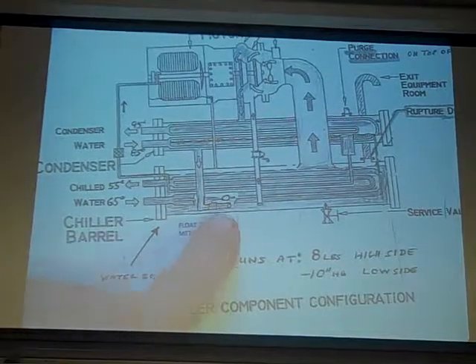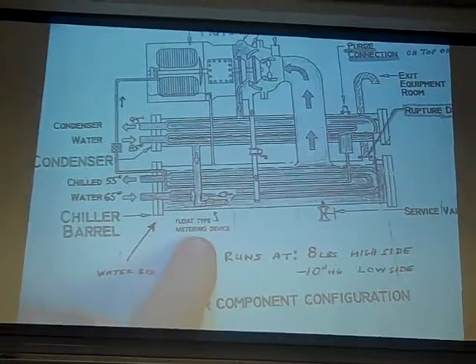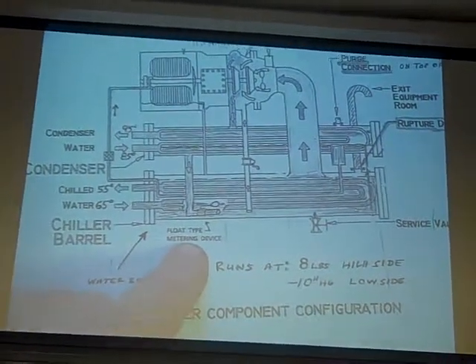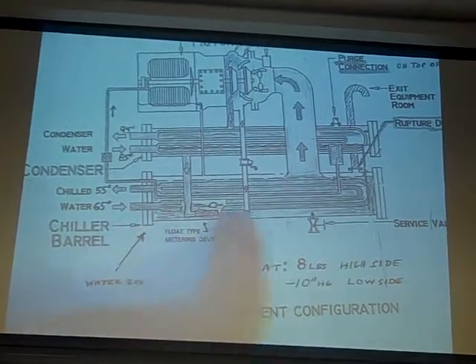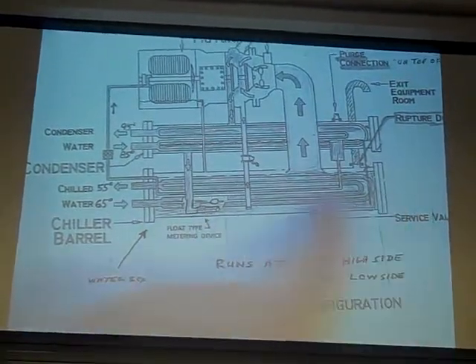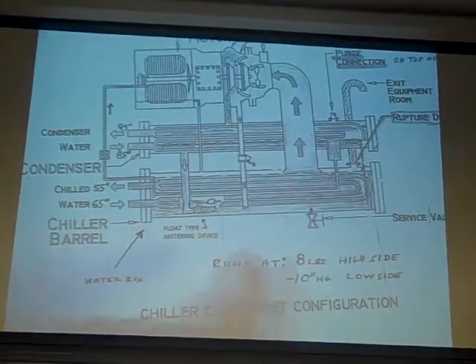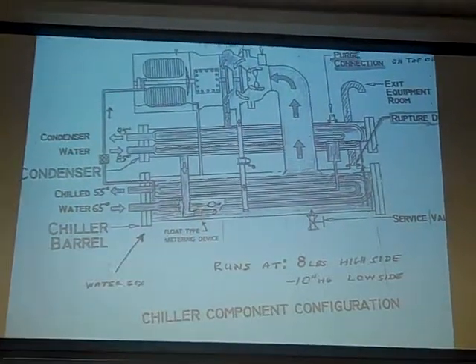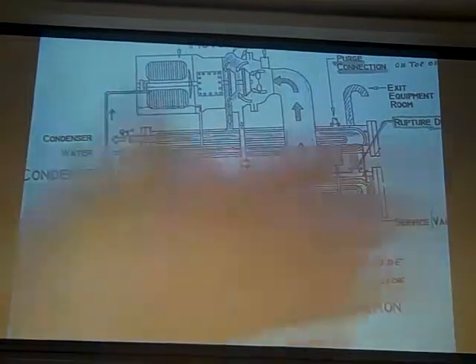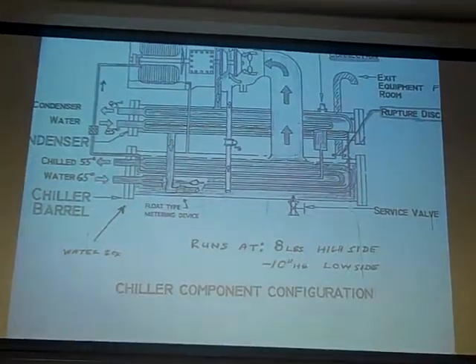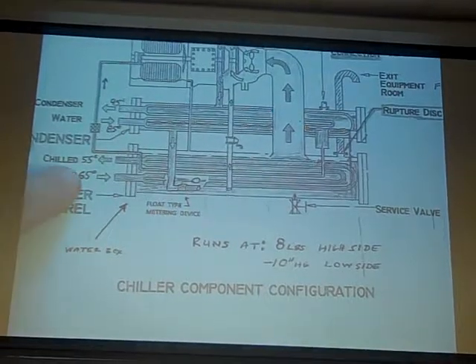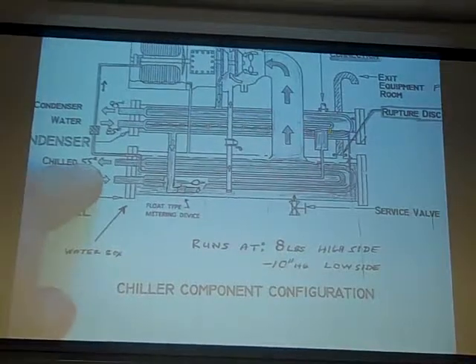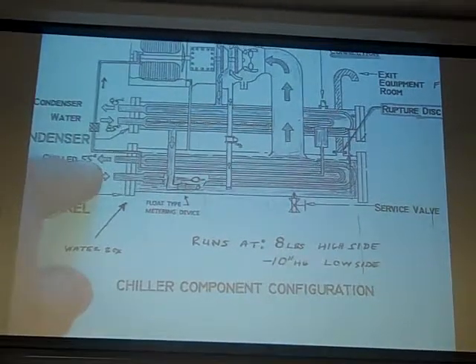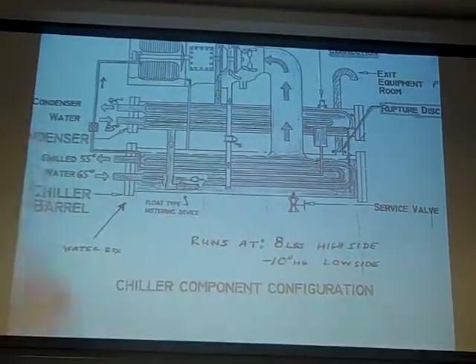They don't use this much anymore. This was using a float type metering device. But typically this bottom down here is going to be liquid refrigerant. It's just sitting in there, boiling off, turning to a vapor, working its way up through across these tubes, getting those tubes nice and cold. You can see your water coming in at 65 degrees, going through here, coming back out at 55 degrees. You drop your water temperature 10 degrees, just in that little short span.